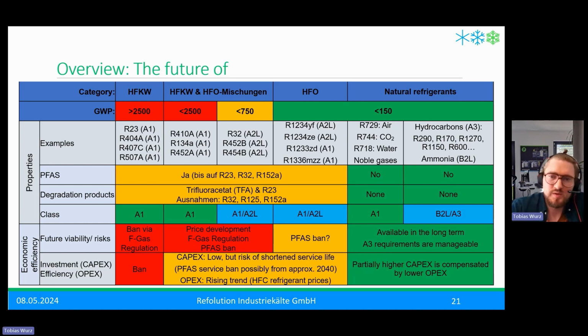What you can see on the right - of course we, as Refolution, promote the natural refrigerants, where we only have one topic: flammability. But as you can see, the lower the GWP, the higher the flammability. The risk of flammability can be handled - it's possible, no problem. It's a challenge for the manufacturer, but it can be handled with a good risk assessment. But all of these HFCs and HFOs have the problem that there are a lot of regulations, like I mentioned in the two topics before, with the F-gas regulation and the PFAS proposal.